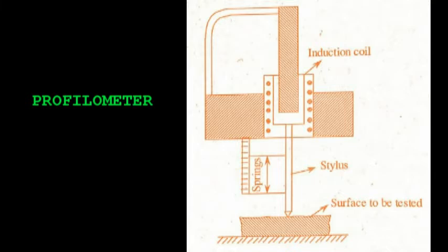The profilometer is an indicating and recording instrument which is used to measure roughness in microns. The principle of the instrument is similar to a gramophone pickup. It consists of two principal units, a tracer and an amplifier. The tracer is a finely pointed stylus.